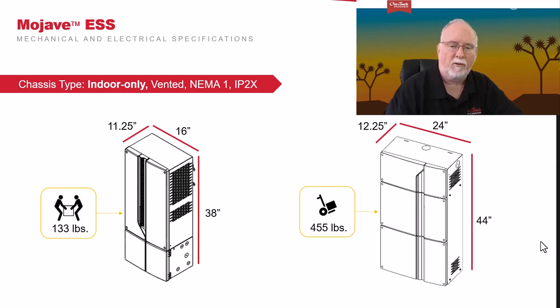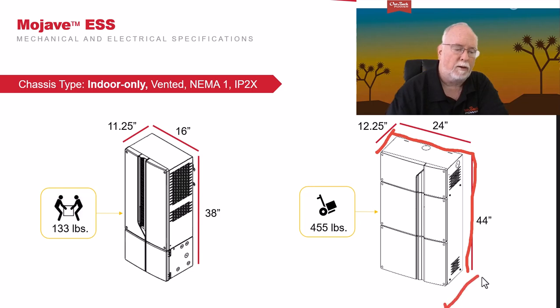Speaking of sizes, this is the Mojave dimensional slide. So the battery system is 44 inches tall, 24 inches wide, and 12.5 inches deep. This allows it to fit easily upon a garage return wall, which is generally at least 2 feet. So the inverter will fit on top of it. Again, it is 38 inches tall, 16 inches wide, and 11.5 inches deep. The two will line up using this pass-through, and this pass-through typically, with a chase in between.